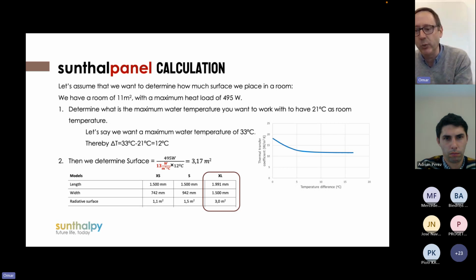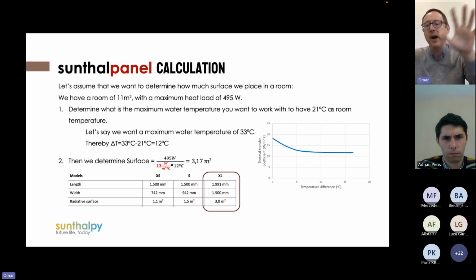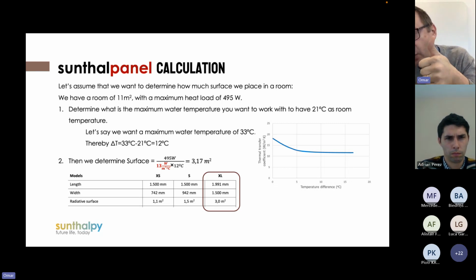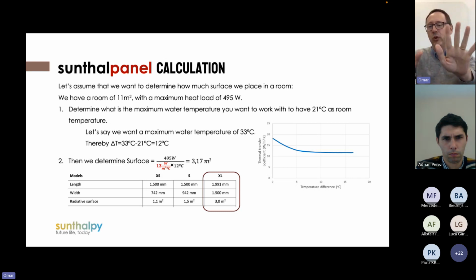If you have that situation, we have a limitation: maximum we can put 2 XL in series. We always try that all our panels are in parallel, feeding them independently. As long as you have a half-inch water pipe and all of them are in parallel, there's no problem, the system will work. If, in a specific case, you are using an existing hydraulic system, the maximum you can put is only 2 in series. I don't know if I'm answering the question, Adrian.